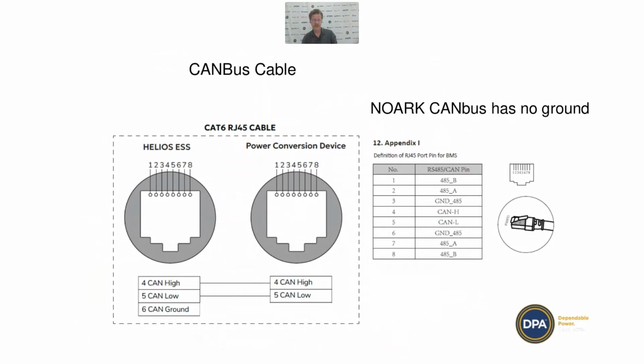Yeah, so this is a good example of that. You can see that we've got CAN high on 4, CAN low on 5, and then the ground, which is 6 or 3, they're all for the RS485. It doesn't seem to always be a problem, but I have seen it be a problem for somebody once. It wasn't working, and then once they removed that, it all came right.